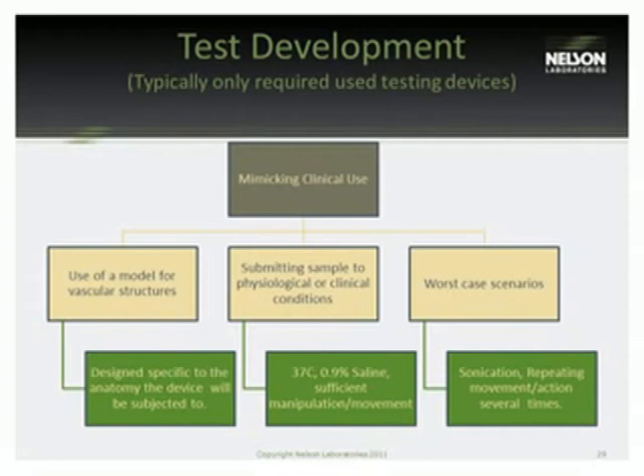There we go. Okay, test development is typically required when testing devices, not so much with liquids, but specific to devices. Again, mimicking clinical use is of utmost importance. The FDA and most other regulatory agencies will really scrutinize the test procedure at hand. They'll want to know that everything in the test procedure follows very closely with the IFU of the product. Use of a model that mimics the vascular structures that the product will be subjected to is very common and usually recommended.